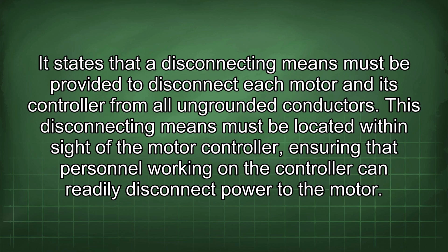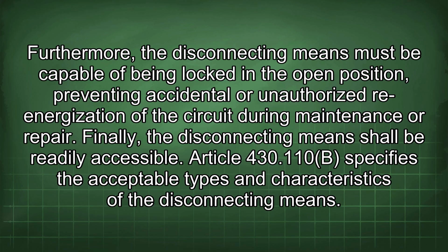This disconnecting means must be located within sight of the motor controller, ensuring that personnel working on the controller can readily disconnect power to the motor. Furthermore, the disconnecting means must be capable of being locked in the open position, preventing accidental or unauthorized re-energization of the circuit during maintenance or repair. Finally, the disconnecting means shall be readily accessible.